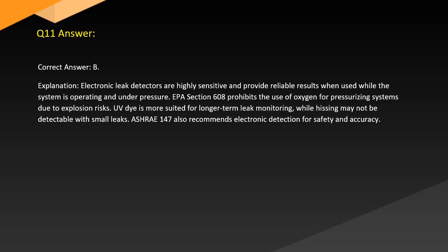Answer. Correct answer: B. Explanation. Electronic leak detectors are highly sensitive and provide reliable results when used while the system is operating and under pressure. EPA Section 608 prohibits the use of oxygen for pressurizing systems due to explosion risks. UV dye is more suited for longer-term leak monitoring, while hissing may not be detectable with small leaks. ASHRAE 147 also recommends electronic detection for safety and accuracy.